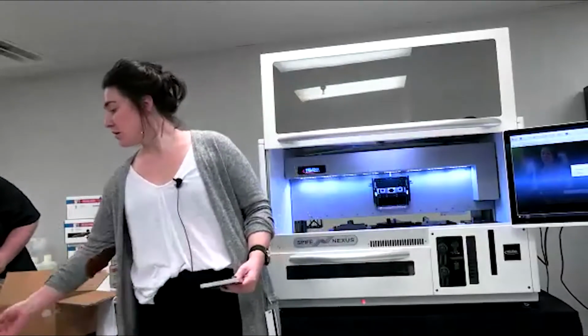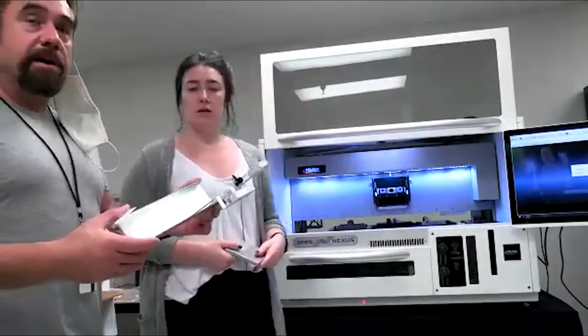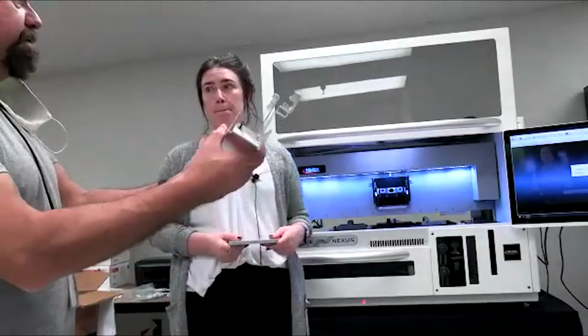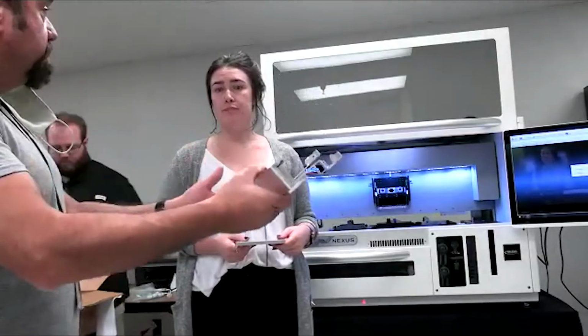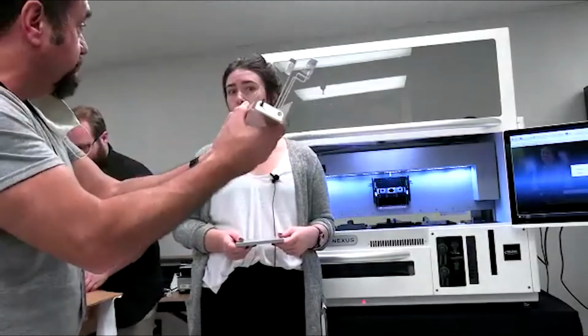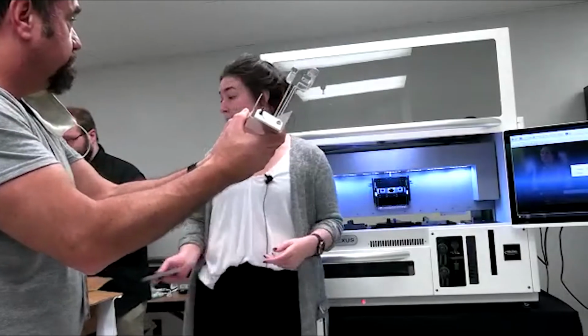Right. Yeah. And then while you're getting those out, if we go back to the bracket that we were talking about, do you recommend that if they move this from their office, once they've set up and done the IQ, OQ on the instrument, and they move it to the customer, they should reinstall the bracket when they move it? Absolutely. When there's no power being supplied to the machine, the pipette and the claw assemblies slide freely, and we don't want them to sustain any damage in transit. That shipping bracket will keep those pieces from sliding, bumping into each other, bumping into the wall. They'll keep everything in pristine condition during transit. So definitely use the shipping bracket when you move it to a different location.